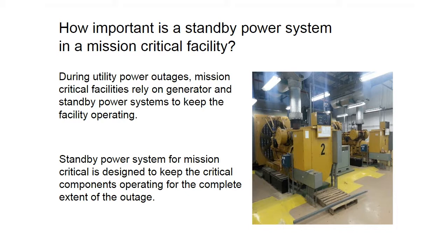An emergency system or maybe a legally required generator are really designed to safely evacuate people, maybe prevent a hazard, by keeping portions of the system operating for certain periods of time, whereas a standby system for mission critical is really designed to keep the critical components, maybe the entire system, operating for that complete extent of the outage. It's not just a short period of time. So that's kind of what we're talking about today. We want to talk about the importance of mission critical standby power systems, some of the requirements, some of the codes, and just give you an overall picture of what it means and how to design a system.